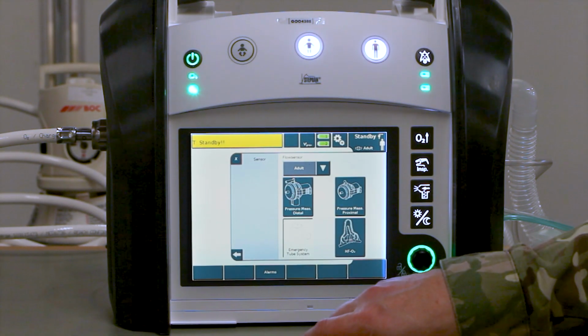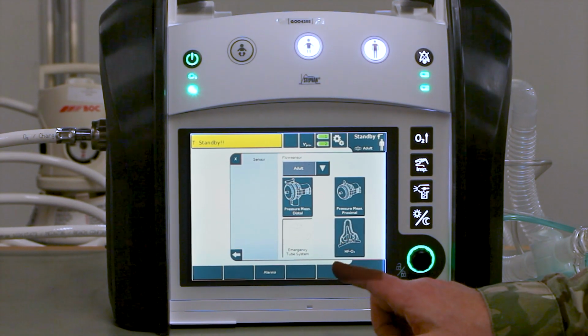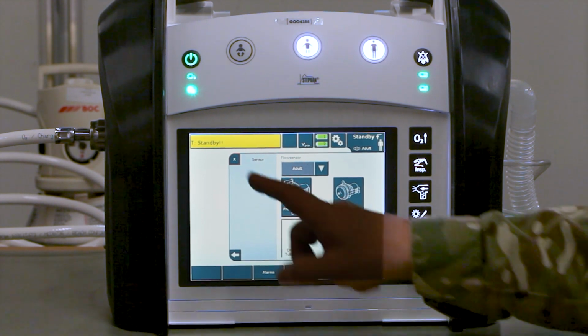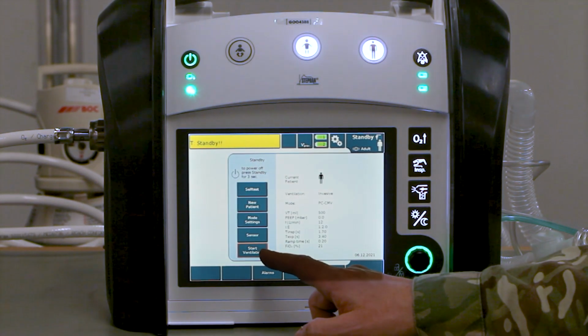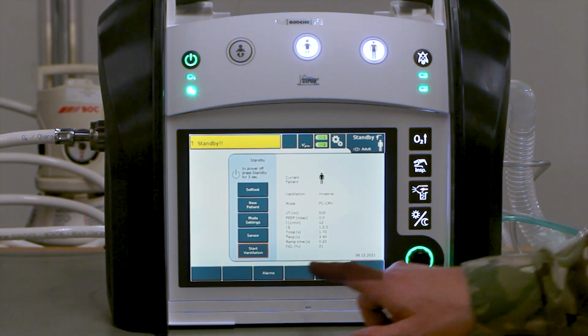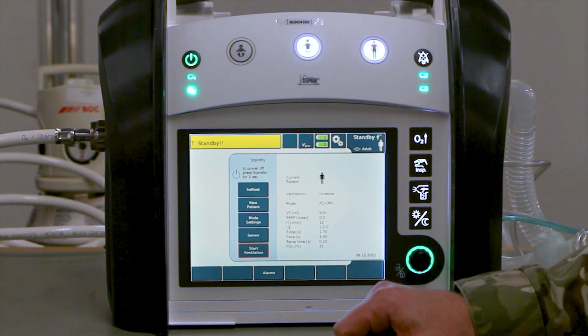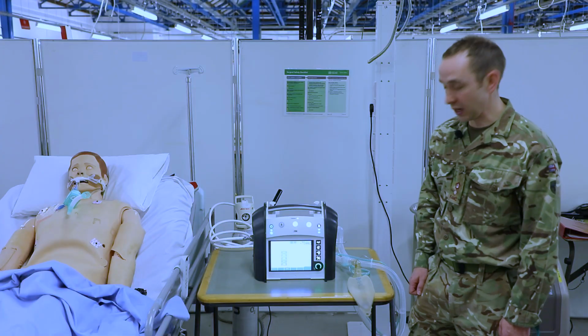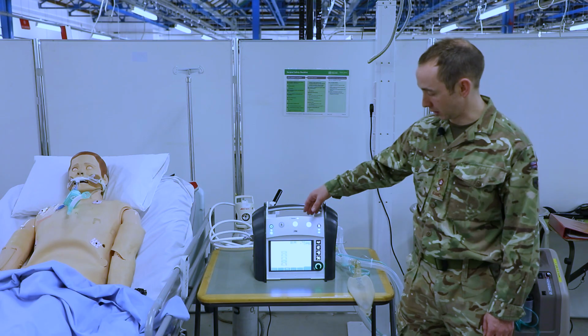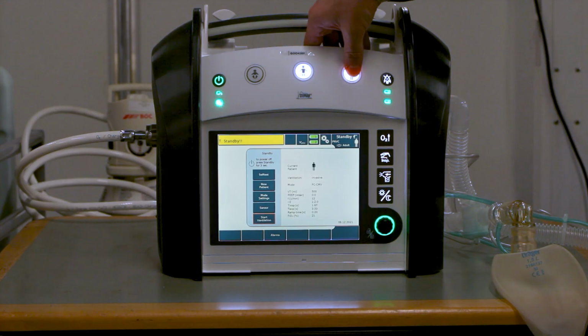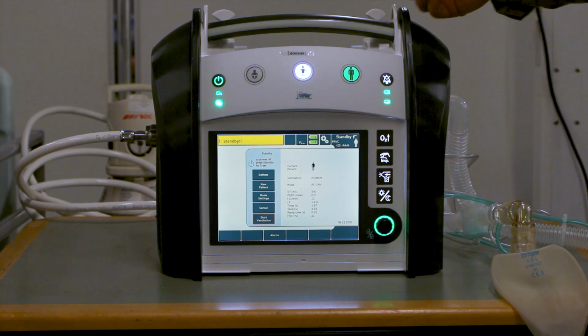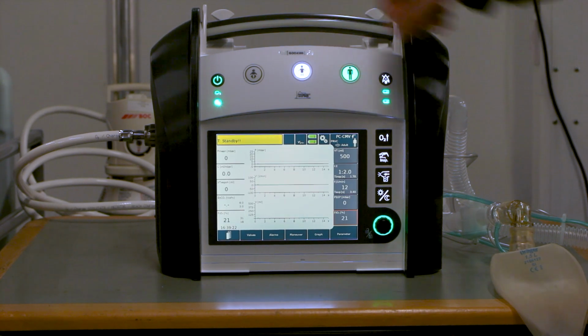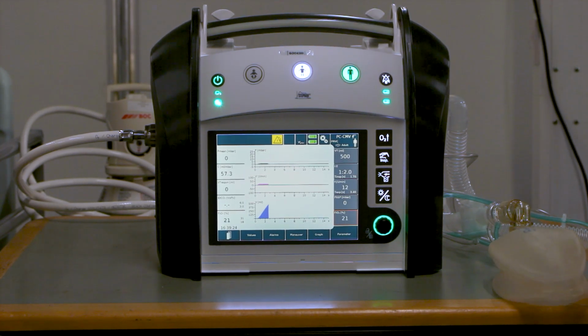There's also a sensor screen which will allow you to set the sensor depending on which circuit you are using. Lastly, you can start ventilation, and that will start what has been preset when you've gone into your mode settings. So now we're going to start ventilation using our fast acting buttons. So we'll press the adult fast start for half a second, it will flash green, press and confirm for another half a second, and that will start ventilation.